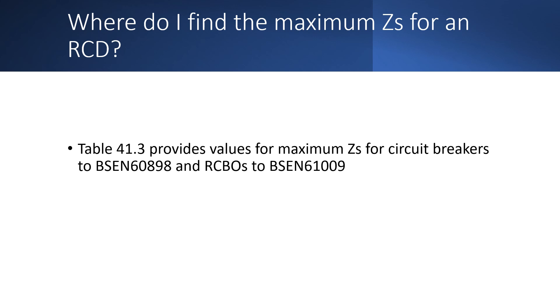Table 41.3 provides values for maximum ZS for circuit breakers to BS EN 60898 and RCBOs to BS EN 61009. For example, a 32 amp type B device, the maximum ZS is 1.37 ohms. However, if we're working on a TT system, it is possible that the ZE alone will be greater than this figure. So how can this be the maximum ZS?